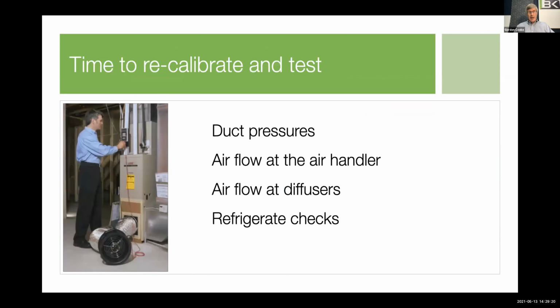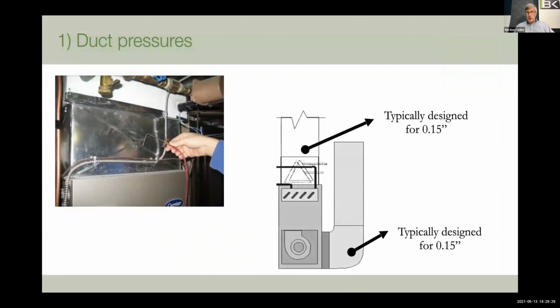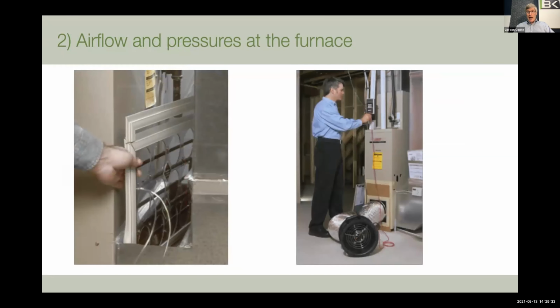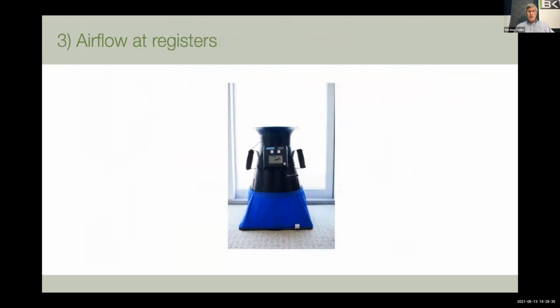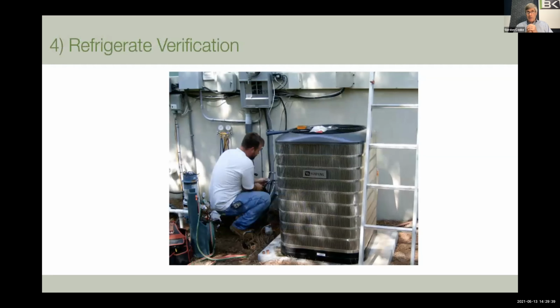And then in about 1 minute I have left, I'm going to say commission your systems. And when I say commission, here's what I mean. Measure duct pressures, see where you're at. Measure airflow and pressures at the furnace. Measure airflow at registers. And most importantly, measure and verify refrigerant charge.